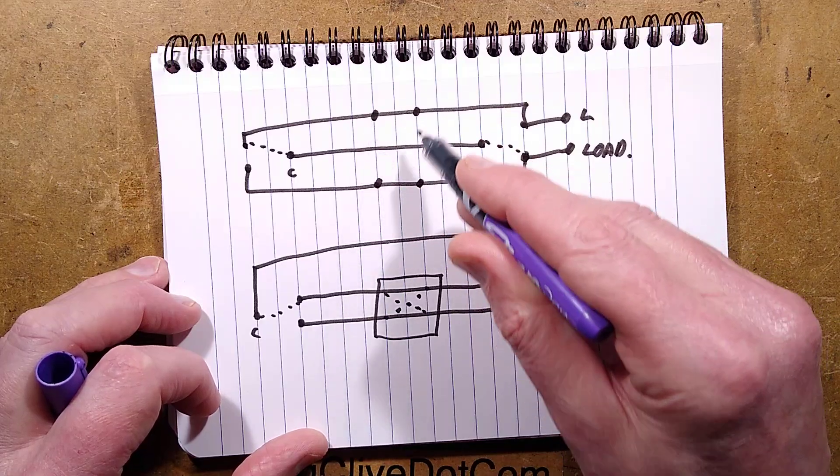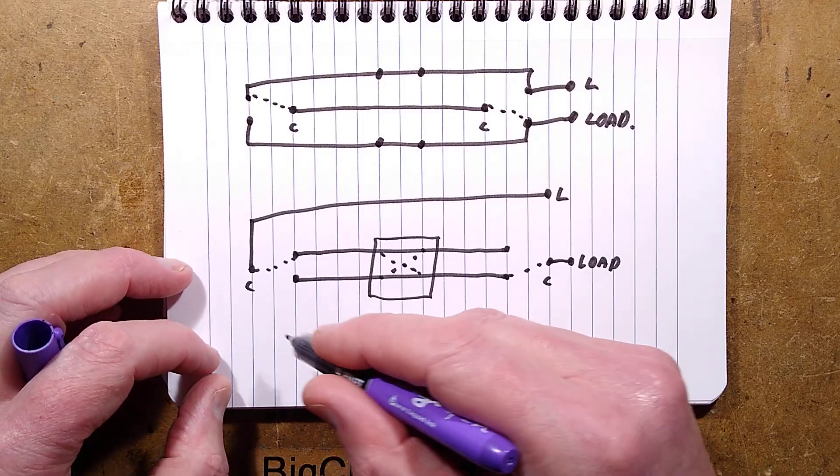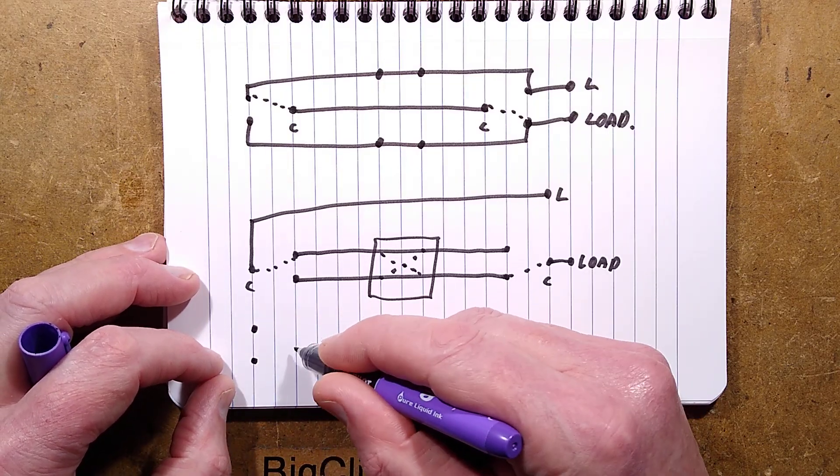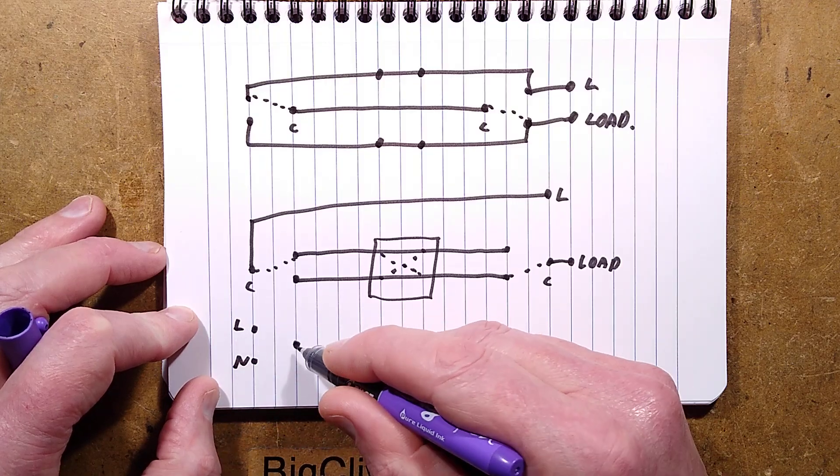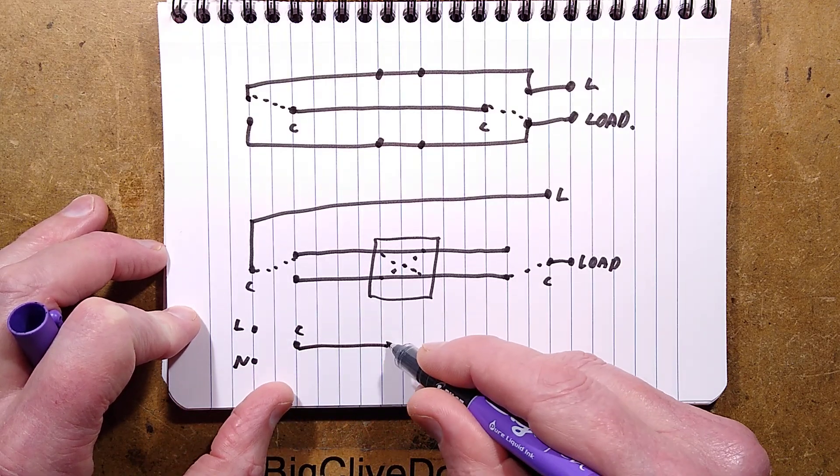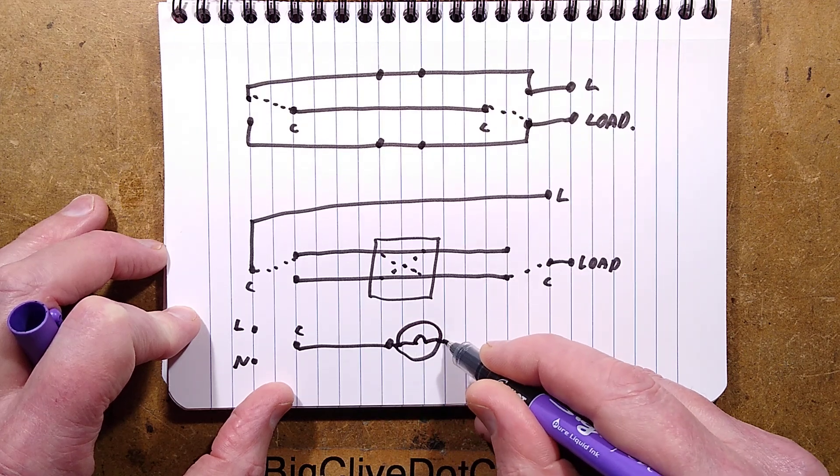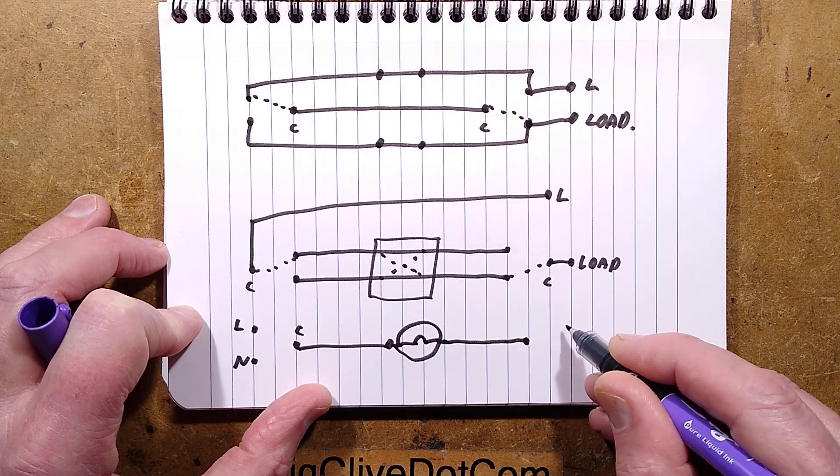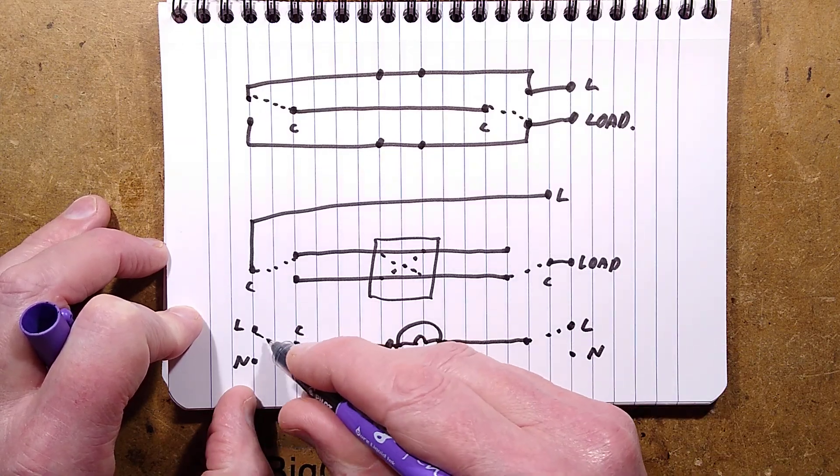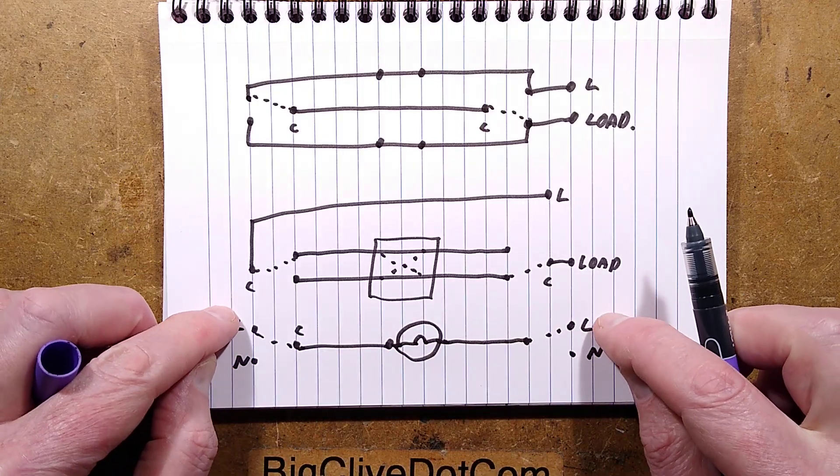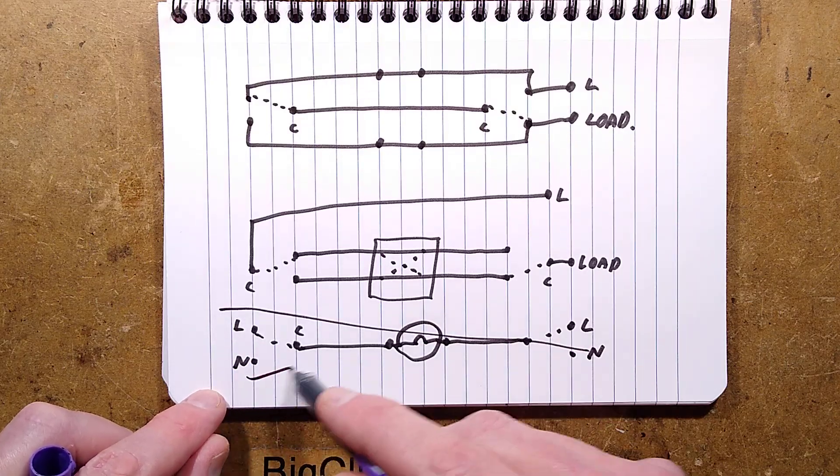The completely non-compliant way - and don't do this - is that in some countries they'll have live and neutral on the L1 L2, and they've got the common connection and then that will go to the light. They go to the other end and they've got live and neutral again. But the downside of this is that if you've got the switches both in the live position, then the light will be off but both connections to the light will be live. This is not compliant in any way but it is done apparently in some other countries.